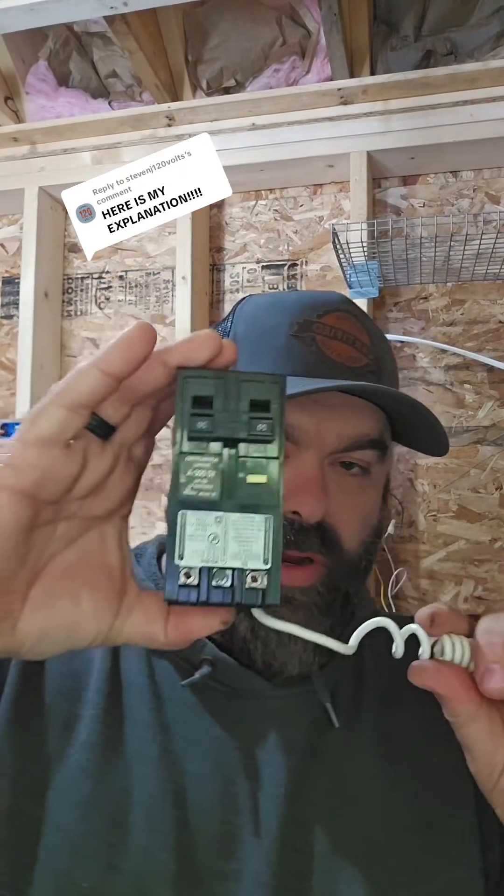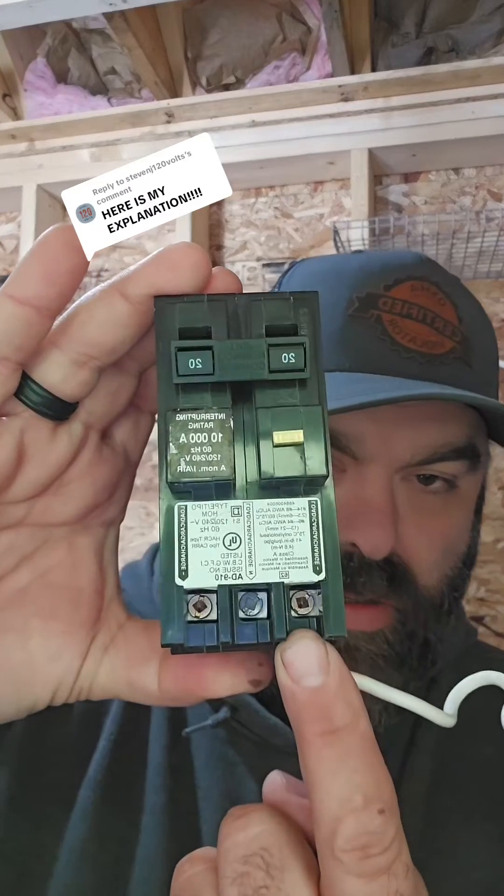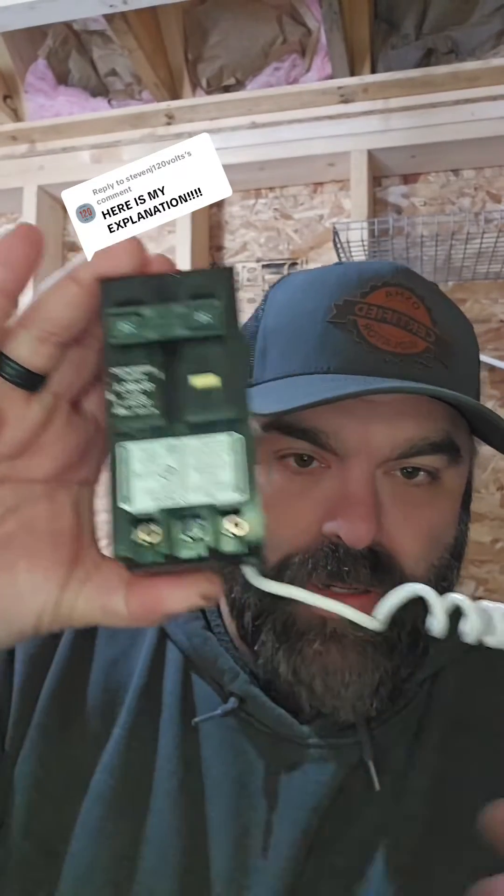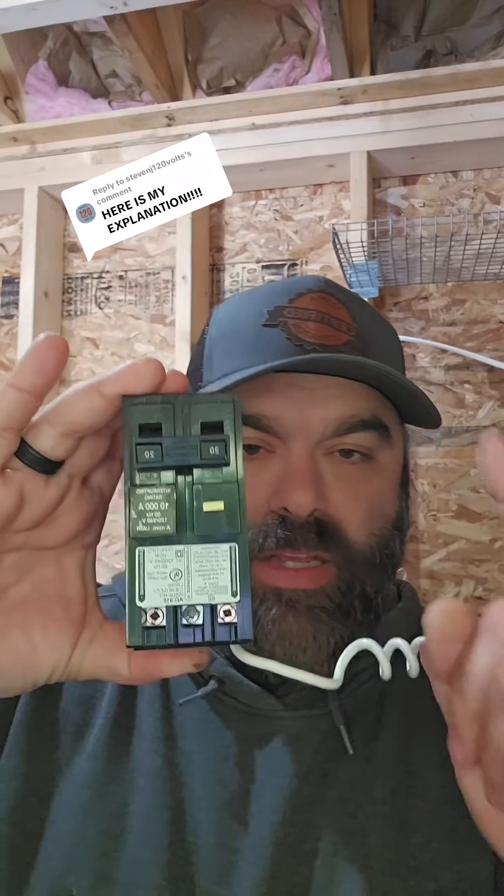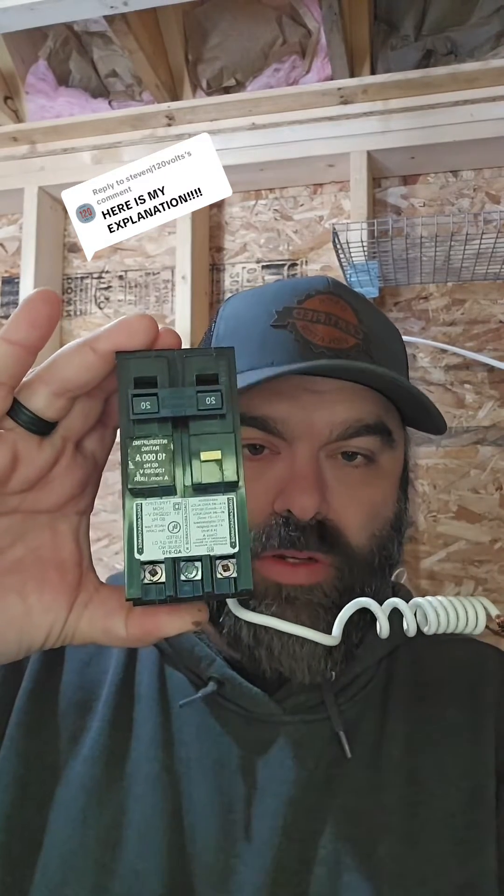And what he's done wrong is when you have a GFI breaker, the hot goes here, the neutral of the circuit goes here, this pigtail goes to the neutral bar. He has run his neutral of the circuit straight to the neutral bar and not back to the breaker. If you want to know why that'd make it trip, let's get into it.